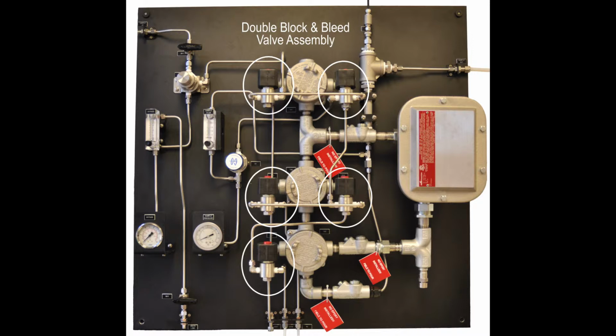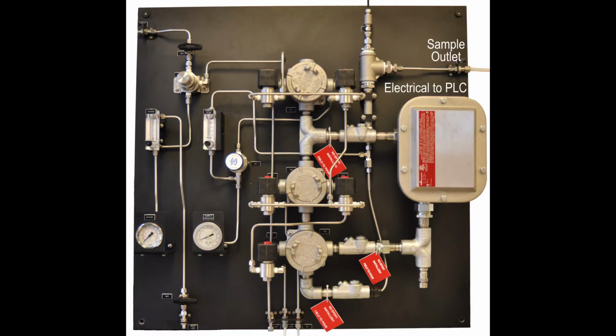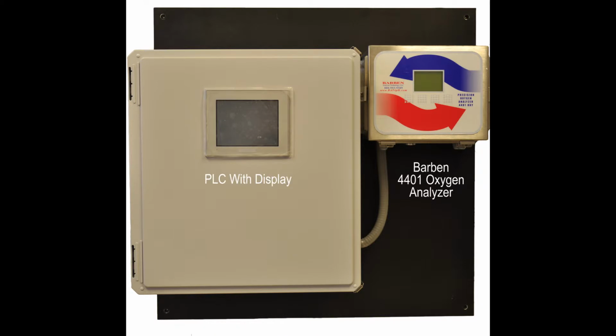This stops the flow of process gas if a power failure occurs, thus limiting the danger of continuous leakage of flammable gas. All electrical wiring back to the PLC and our analyzer is in the explosion-proof box at the right. The PLC and the analyzer are mounted outside of the hazardous area for easy access by the customer. Now, let's switch over to the PLC and check the response time of our sensor.